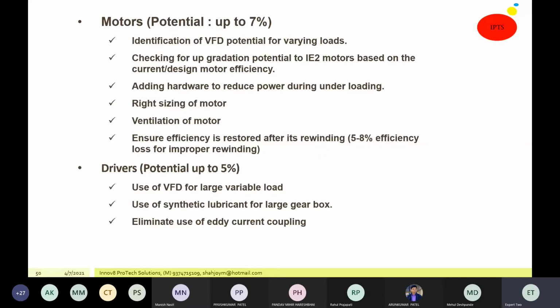And after rewinding also, people don't measure the efficiency. If we measure the efficiency, we will find some drop in the efficiency, then perhaps replacement of the motor will be more economical. Similarly, drivers like VFD, or maybe lubricant in the driver, or large gearboxes, and eliminate use of eddy current coupling. So these are my advice based on my experience.